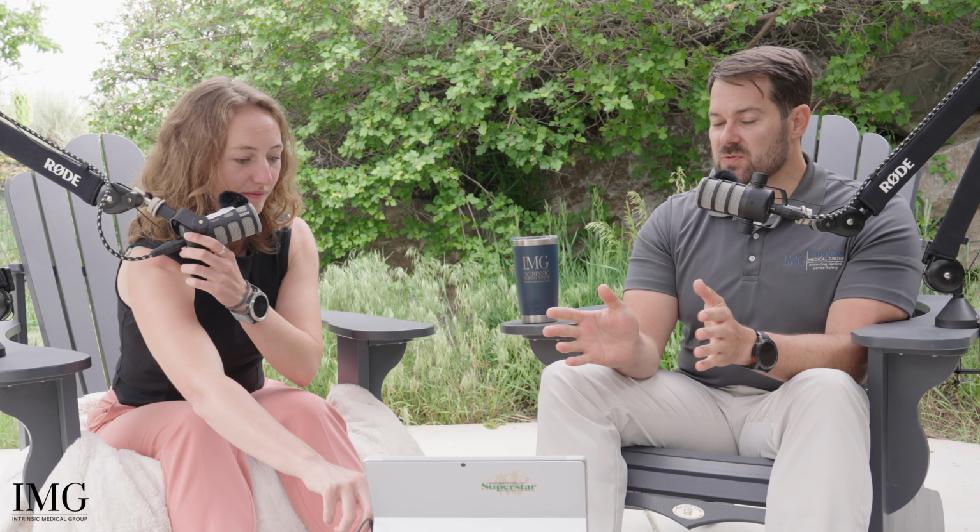Very good question, and a good high-level question to step back on, because I know I dive down into too many details here. All good content. So when we step into an implantation, first off is, how is my device going to be used and exposed to the patient? So that's going to mean that I need to expose it to that same type of situation. So if we need muscular, bone, subcutaneous tissues, that will depend on where you're going to put the implant, and that will also generally lead to what model you want to use.